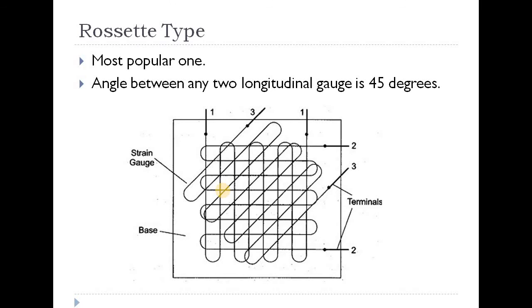The second type is rosette type — it is the most popular one. It measures strain in multiple directions. The angle between any two individual gauges is 45 degrees. So one gauge measures in one direction, the second at 45 degrees, and the third at another 45-degree increment.